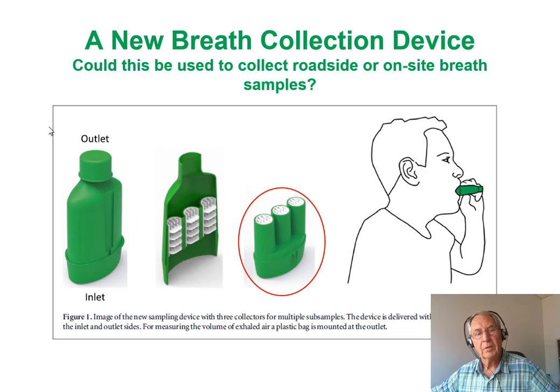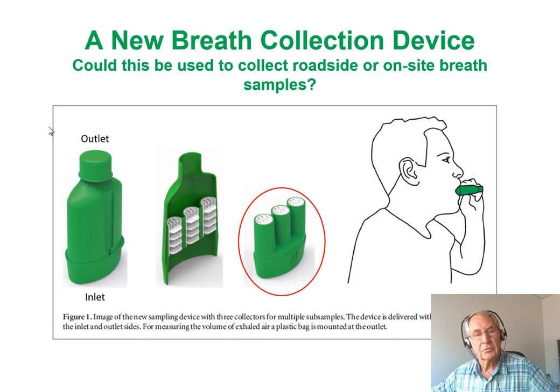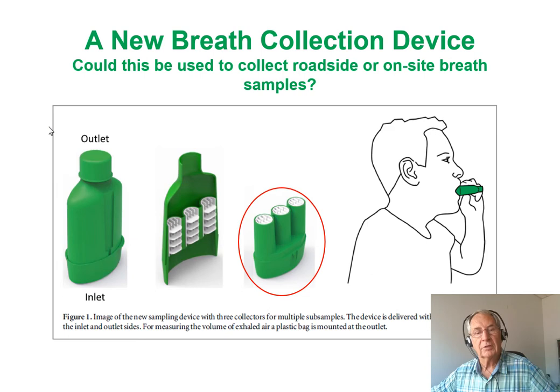This new device is shown here. It's a simple, small device with an outlet and an inlet. The person providing the sample removes the inlet and outlet covers, places the larger opening to their mouth, and exhales slowly about 10 times into the device. Inside the device, cut away here, you can see there are three collectors in a tortuous pathway for the breath to go through, with lots of surface area where particles are collected. Having three collectors means one sample is split into three: an A sample, a B sample, and a C sample.